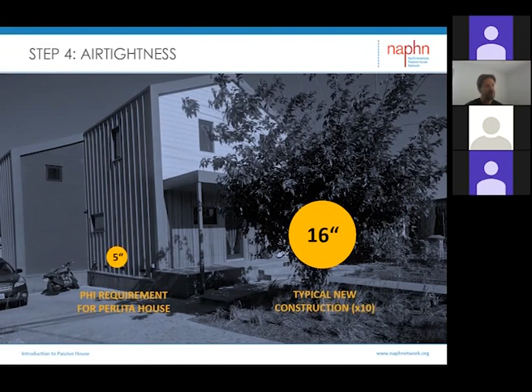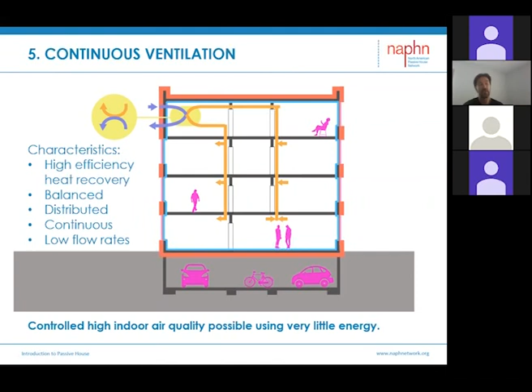It's not possible to have proper indoor air quality without mechanical ventilation, unless you're outside or your windows are open 24/7. But if your windows are open 24/7, you're not comfortable. So in a comfortable building, in order to have proper indoor air quality, you need mechanical ventilation. In a passive house building, the reason you need an airtight envelope is that you know the exact amount of pressure you need to bring, because you know no pressure is going to come from building leakage.